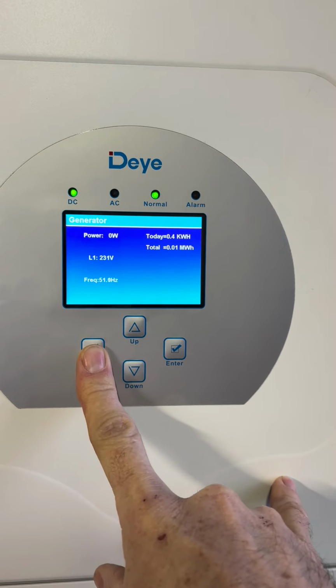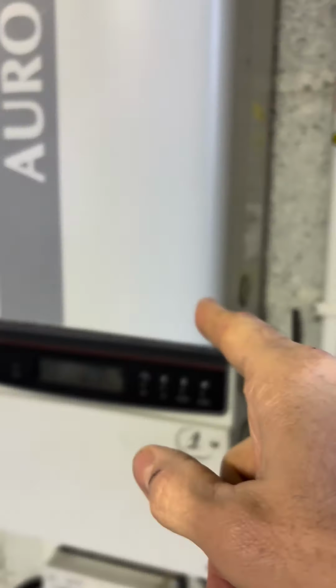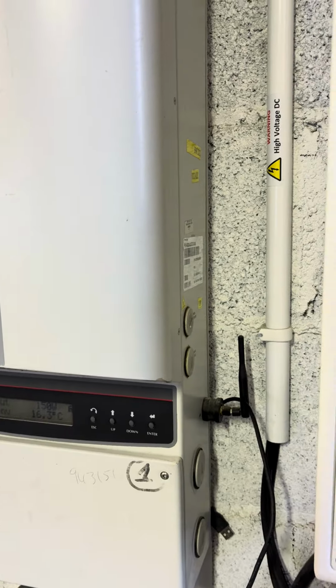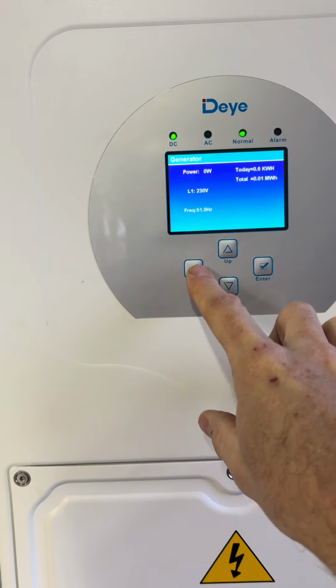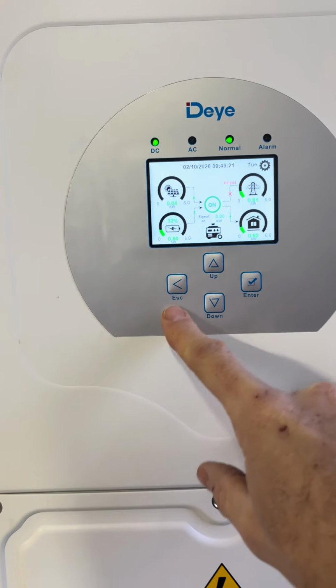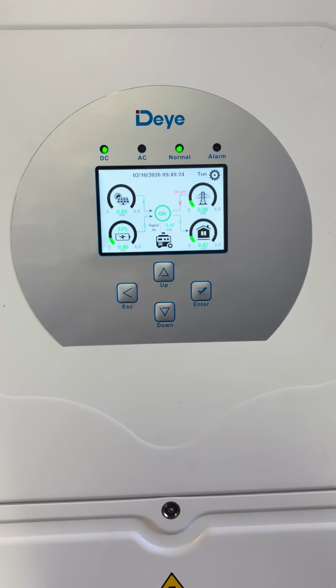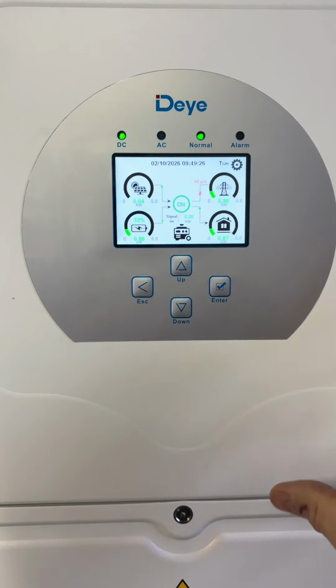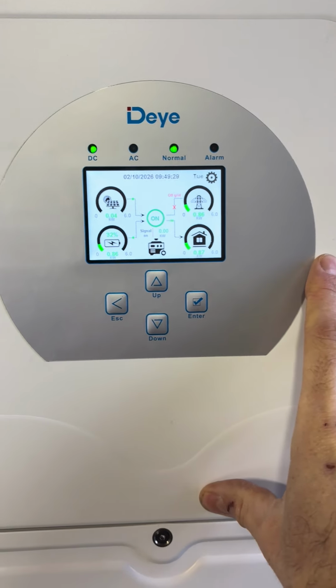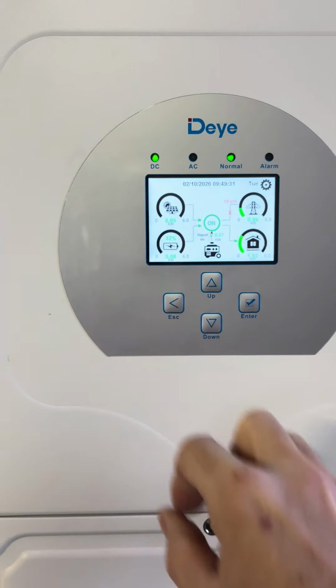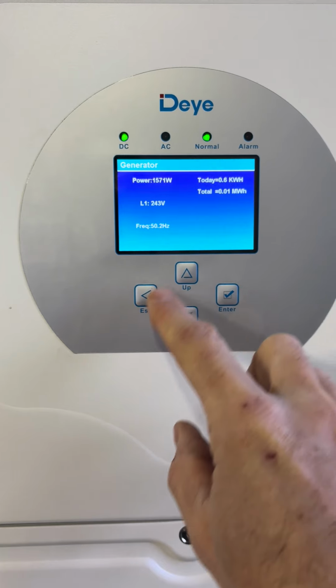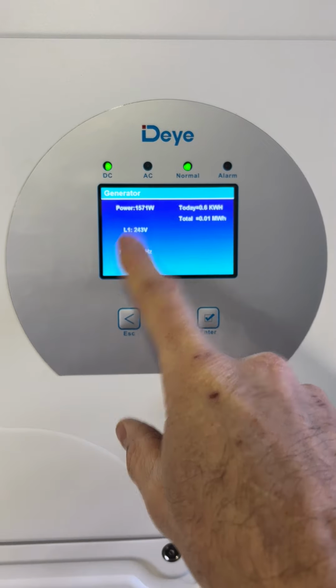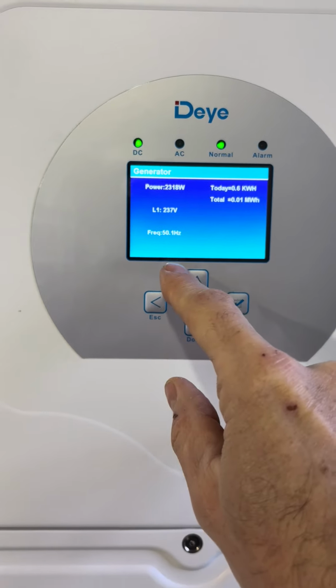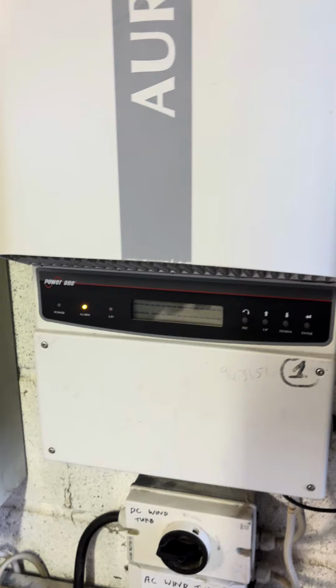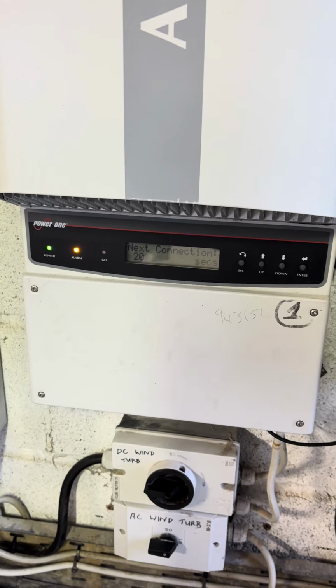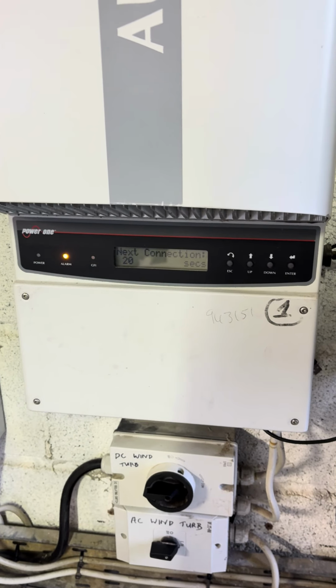What I expect to happen now is once the generator synchronizes, it will reject the Aurora turbine again, because the microgrid is going to fluctuate a bit. And it has to change over, so it will go from inverter grid here to generator. Okay, so our generator is loaded now. Our voltage is stabilized out, 243, 50 hertz. The wind turbine is disconnected, and it's going to attempt to reconnect again now in 20 seconds.